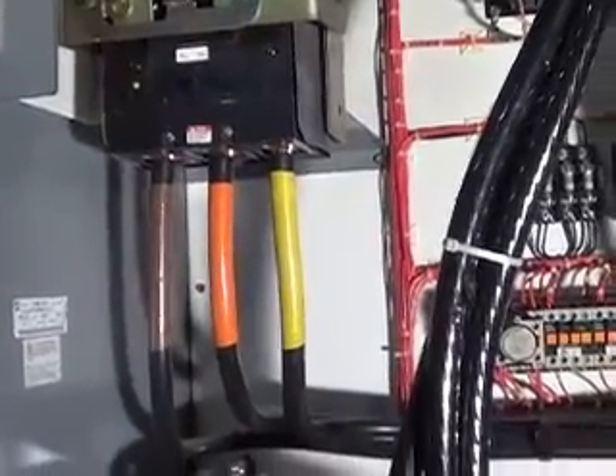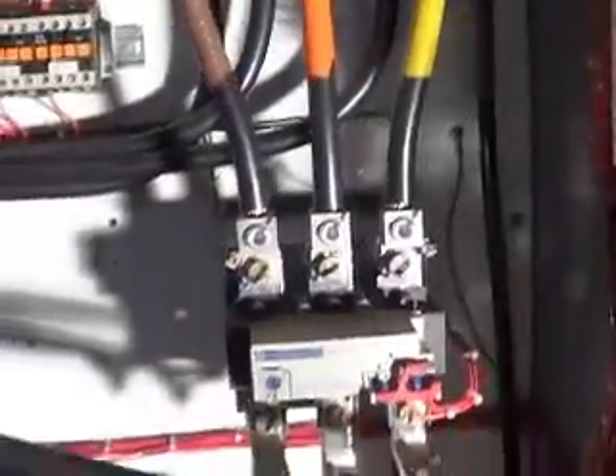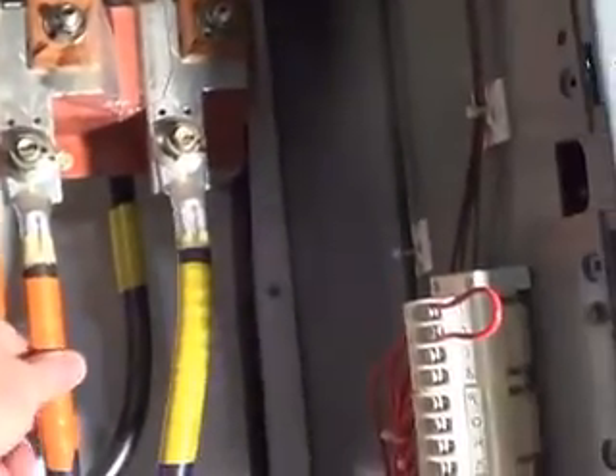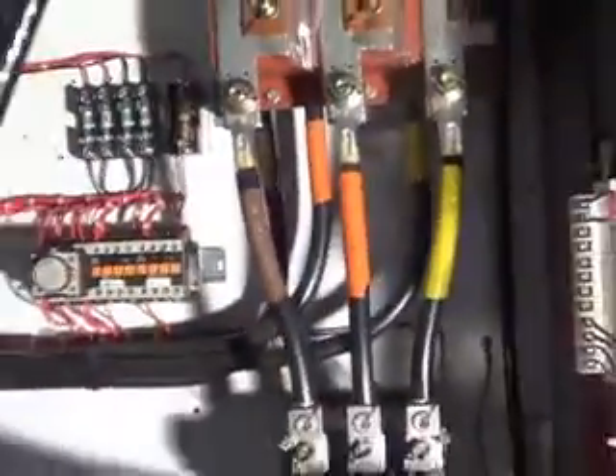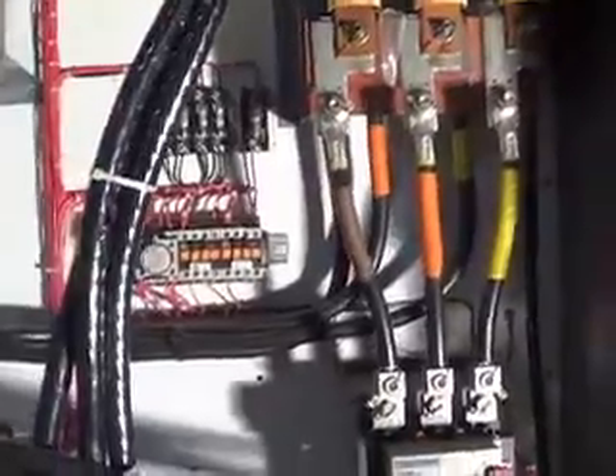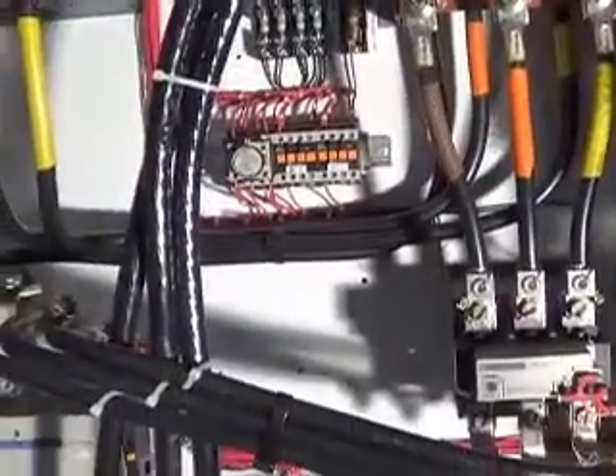A lot of times they bring in control power from another source, and you want to check all your connections. You look for discoloration, just like any metal stuff, the insulation. I've found things functioning that had all the insulation burned off and the wire was still there, black and charred, and the equipment was still working.